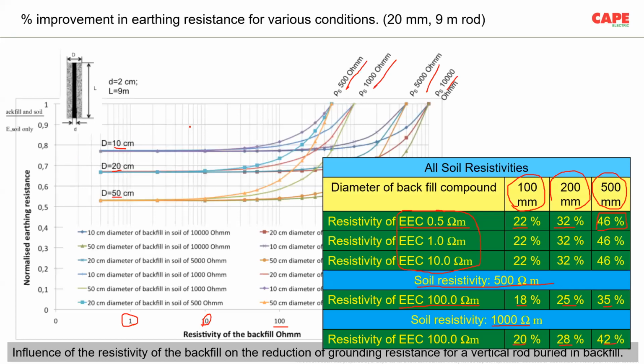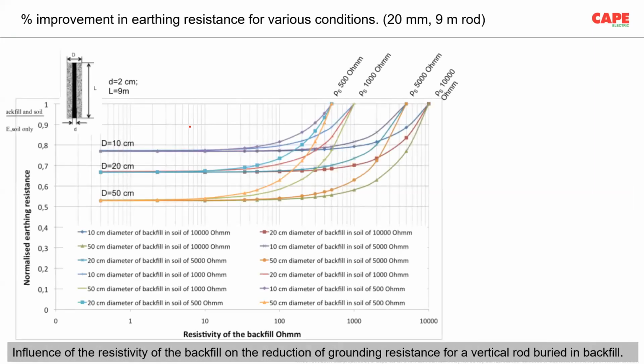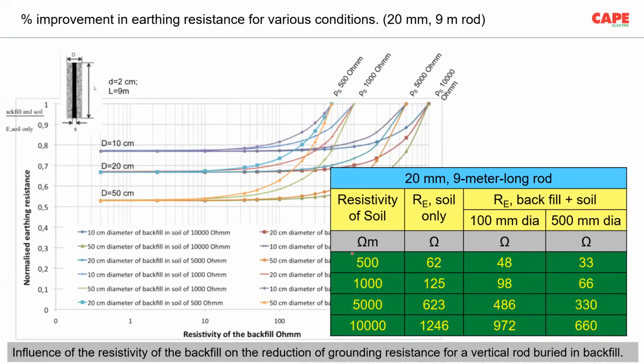So these reports will be published in that particular blog, which I will give you later on. Now, I have made a comparison. Imagine the soil resistivity of 500 ohm meter. In normal condition, a 20 mm rod 9 meter long will give almost 62 ohms RE resistance. If you fill all around the electrode with 100 millimeter dia earth enhancing compound, you get about 48 ohms. If you fill all around the electrode 500 millimeter dia, you get a value of 33 ohms.